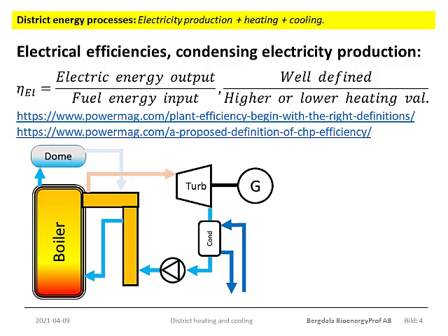The hot gases from the combustion in the boiler escape through the flue, and here I've only indicated the first parts of it. Following these first parts would be the flue gas cleaning system, the flue gas fan and the chimney. But I've skipped all that for the moment since it is not relevant for this module. To run the turbine, which in turn runs the generator, we first extract steam from the dome. But that steam is saturated, because in the dome there is an equilibrium at the boiling point, and the boiling point is set by the pressure.